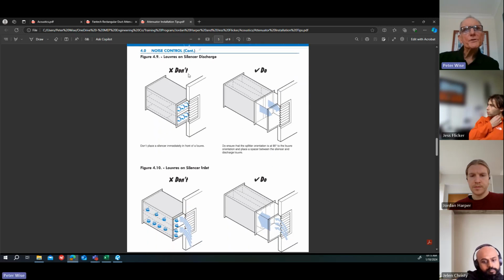Louvers on a silencer discharge. Sometimes they're calling it a silencer here. An attenuator and a silencer are the same thing, so it's calling it a silencer this time. This one has got horizontal splitters. It's very close to a discharge louver, and that's just not working. It's causing too much turbulence at the outlet.